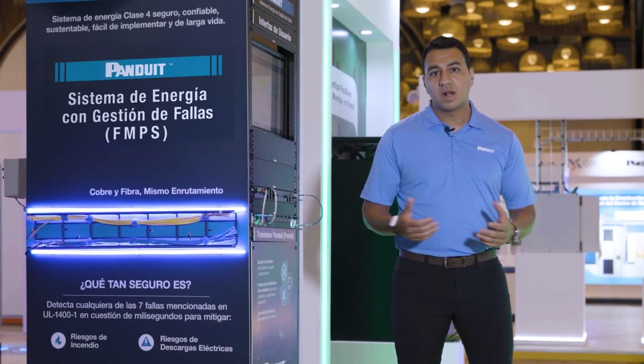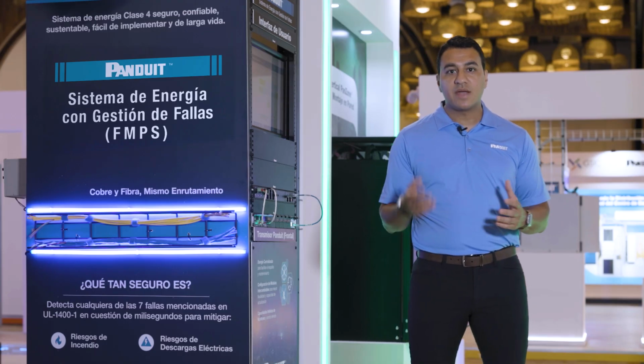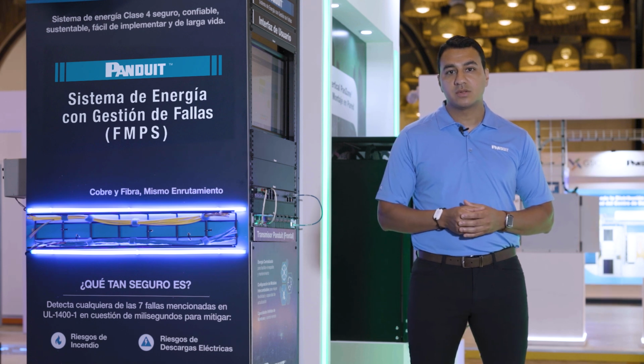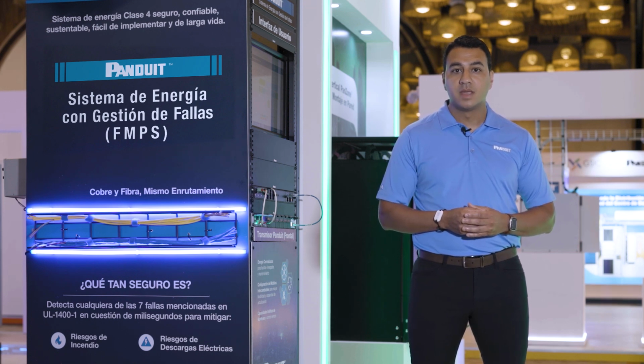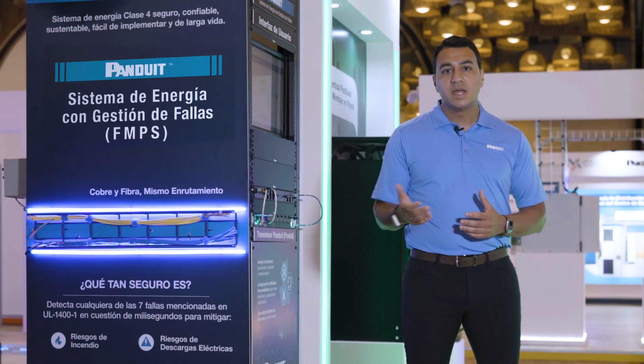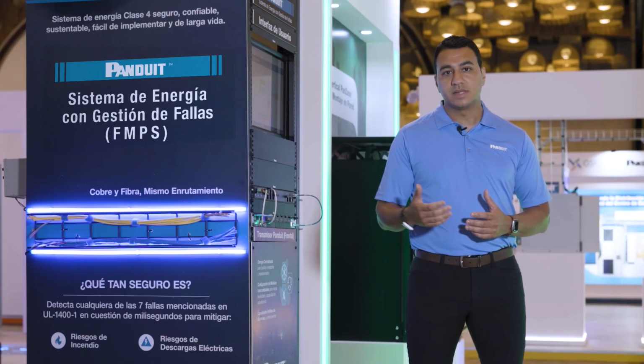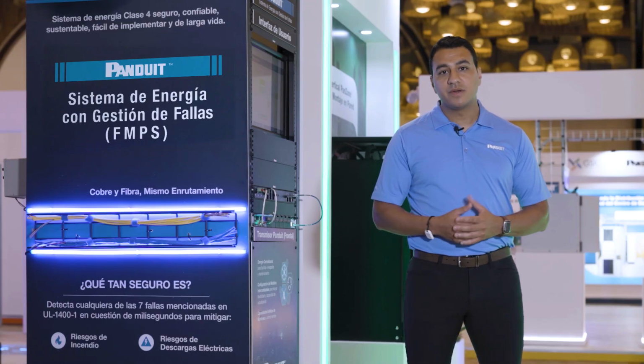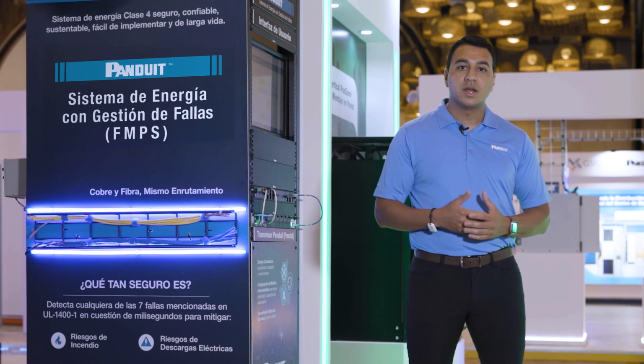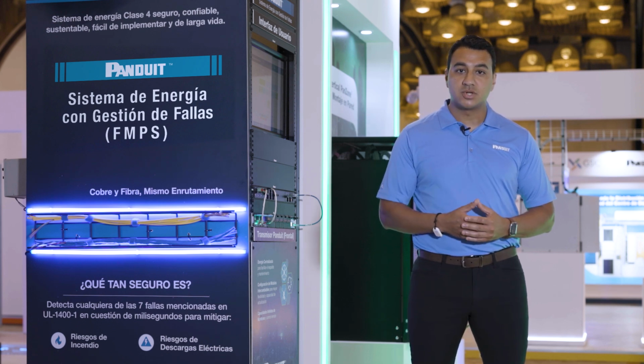Let me first explain what Class 4 means. Traditionally, we have three classes of power in the National Electrical Code in North America. Class 1, you're all familiar with. It's basically what's running inside our buildings. It's up to 600 volts. It has to run in conduit. It needs to be run by electricians.